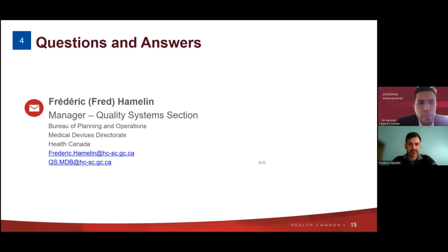The last one, we don't have a name for this. It was sent by an anonymous attendee, but they are basically asking, in the case of Canada, has Health Canada used ISO 13485 and the audits of this ISO 13485 to oversee local distributors of medical devices or local manufacturing sites? So this would be both locally or those that are sent abroad. Right. So yes and no, or sorry, no and yes.